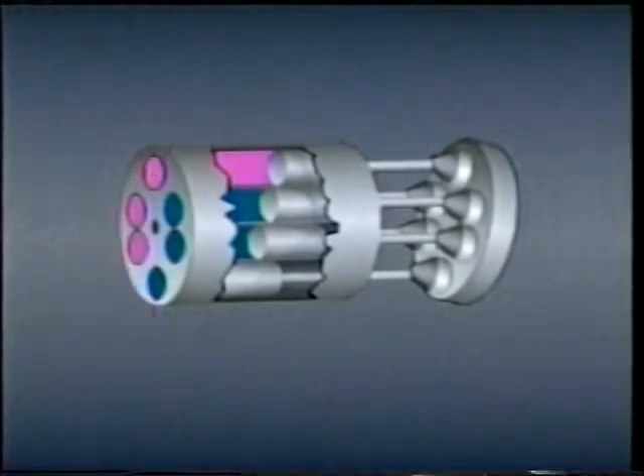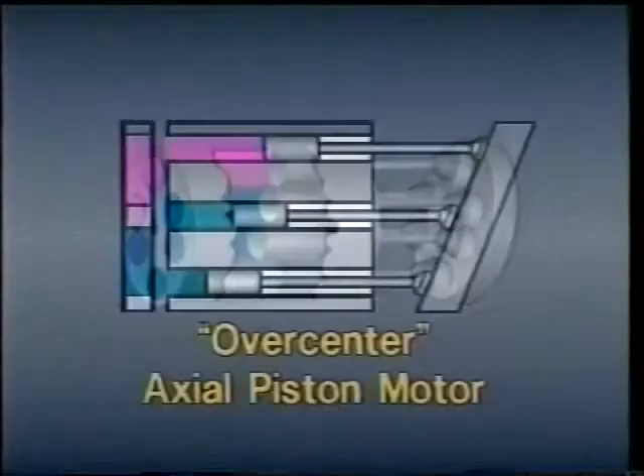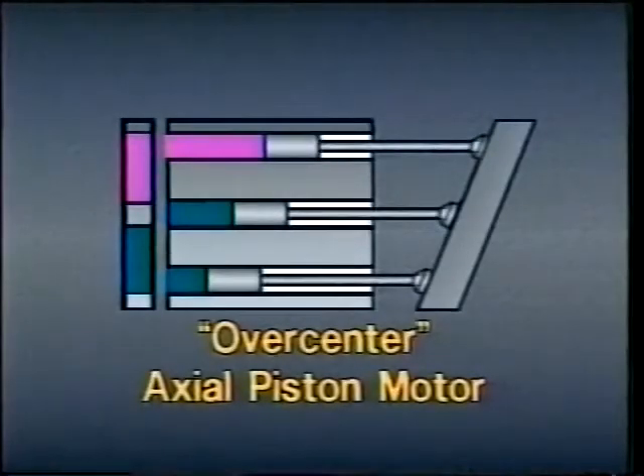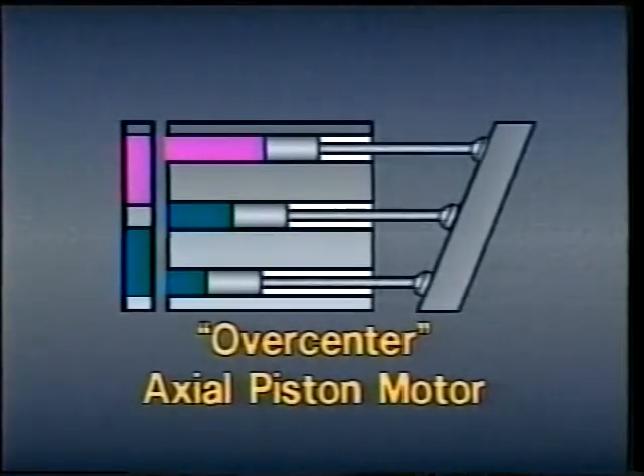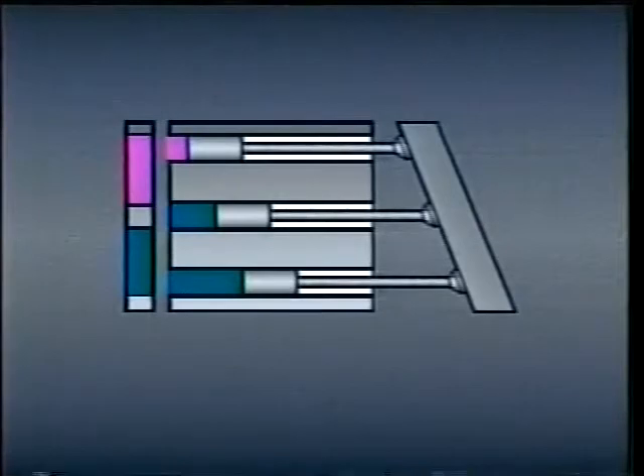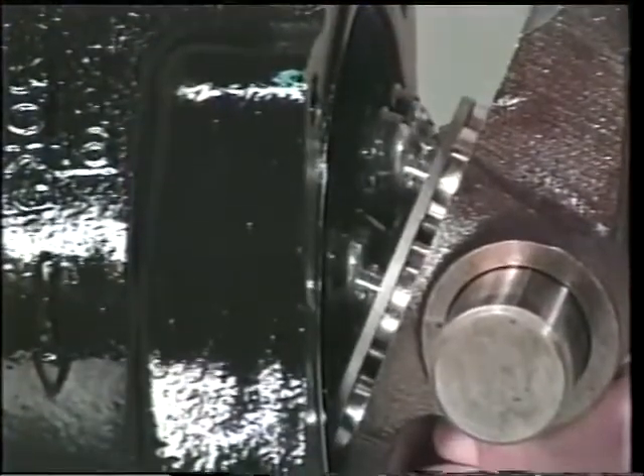Unlike vane motors and gear motors, piston motors can be reversed without changing the direction of flow through the motor. This type is called an over-center piston motor because all that's needed to reverse the direction of rotation is to tilt the swash plate past or over its center. As the swash plate is tilted toward vertical, the motor displaces less and less fluid. When the motor is restarted with the swash plate tilted over center, the piston shoes go back the other way, turning the cylinder barrel in the opposite direction and reversing the direction of the motor shaft.